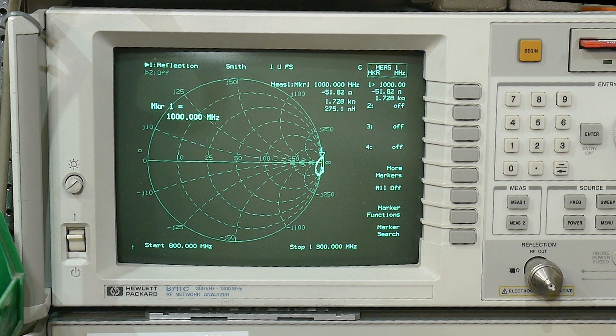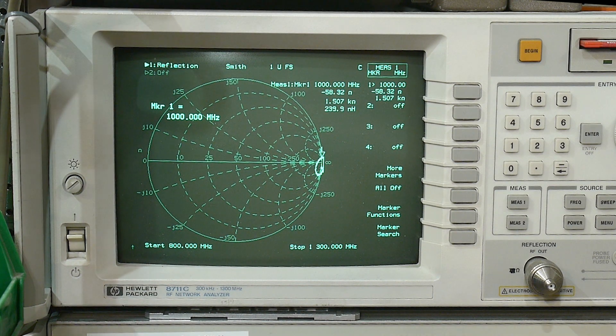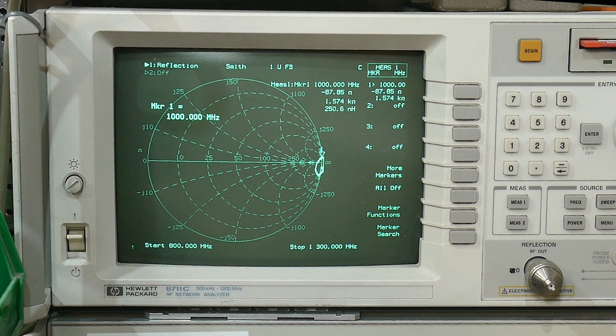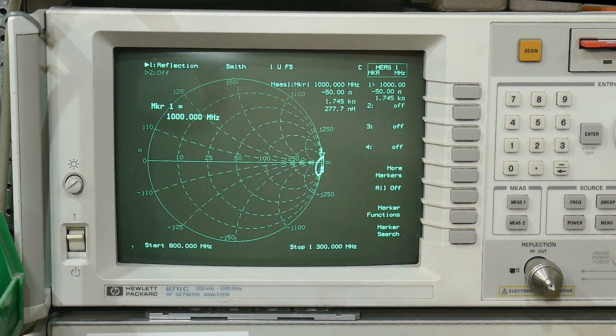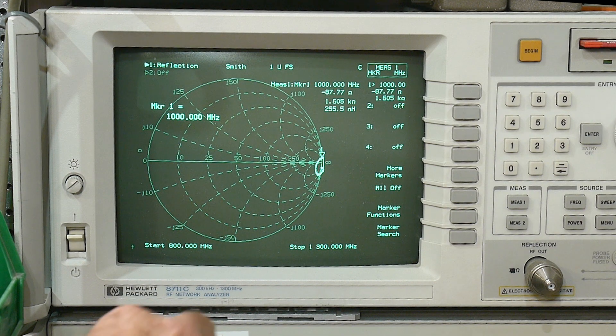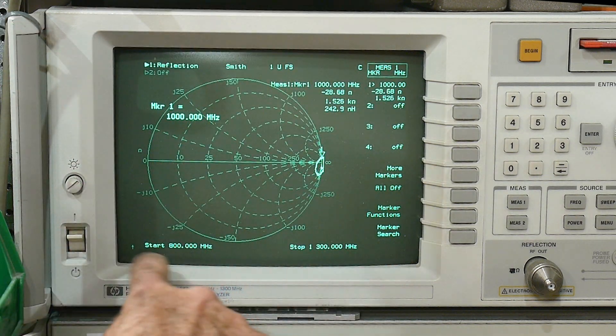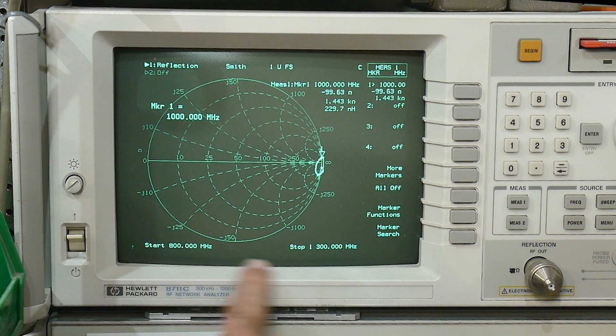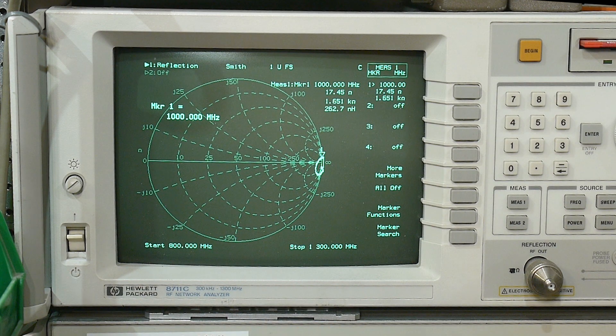So I thought I would expand on what I was doing and show you some examples of coax loss. And so we are going to be using a vector network analyzer. I'm going to be going between 800 and 1.3 gigahertz. All right.